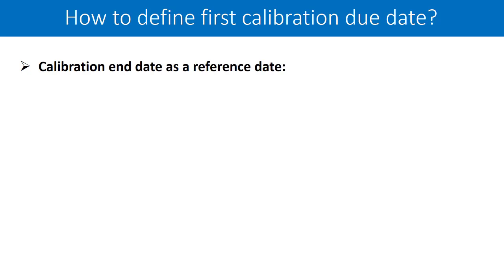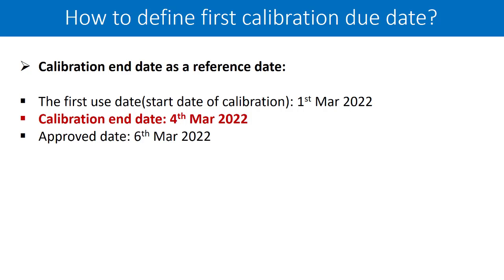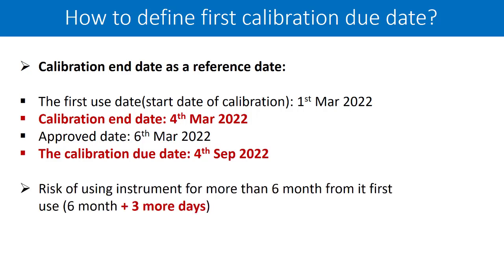Let us talk about the second approach — using the calibration end date as the reference date. The start date of calibration, meaning when the instrument was used for the very first time, is 1st March 2022. Calibration end date is 4th March 2022, and the approval date is 6th March 2022. Against the end date, adding 6 months gives a calibration due date of 4th September 2022. There is still a risk of using the instrument for more than 6 months from its first use — in this example, 3 more days of usage are possible. So this is again not a conservative approach in its nature.